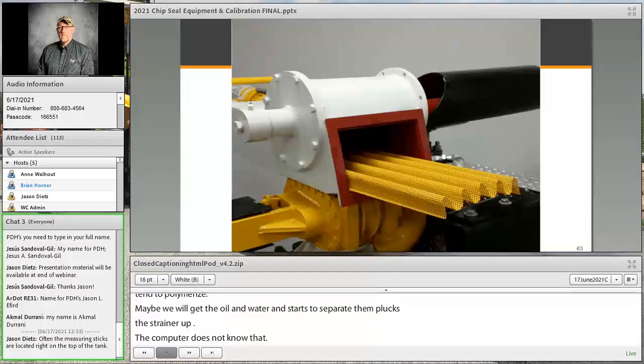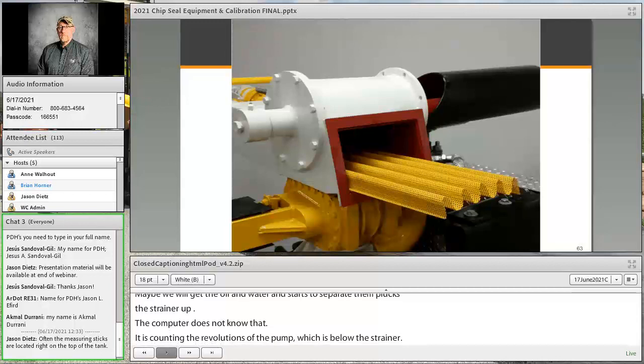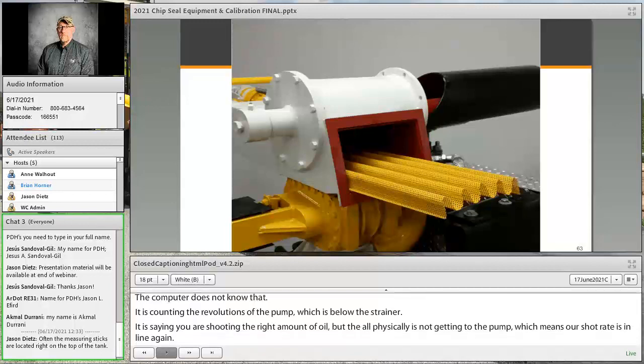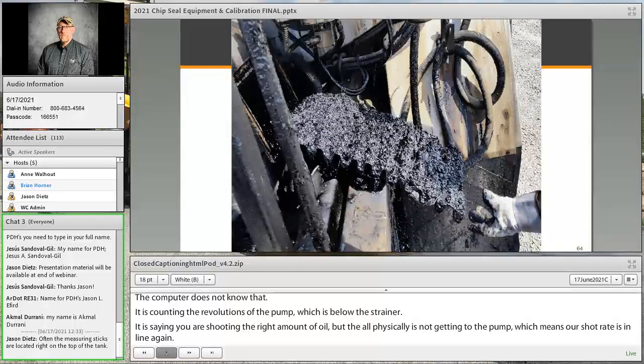I'll tell you that probably 8, maybe 9 out of every 10 phone calls I get during the summer where somebody says their pump isn't spraying the right amount of oil, once they clean the strainer, it sprays good again. So we've got to keep those strainers clean. If you pull your strainer out and it looks like this, you're not shooting the right amount of oil.